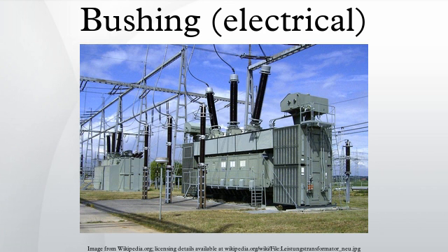Bushing types. Porcelain insulation. The earliest bushing designs use electro-porcelain for both indoor and outdoor applications. Porcelain is impervious to moisture once sealed by fired glaze and is low cost and flexible to manufacture. The main disadvantage with porcelain is that its small value of linear expansion has to be accommodated by using flexible seals and substantial metal fittings, both of which present manufacturing and operational problems.